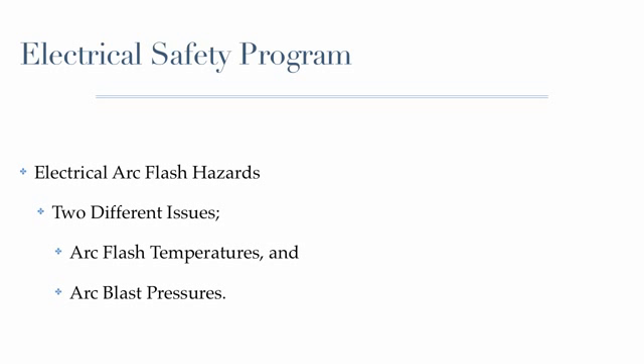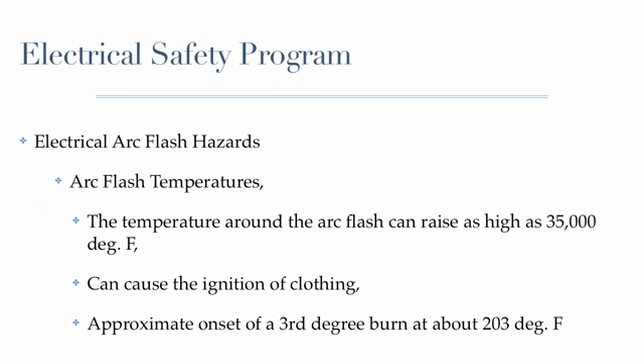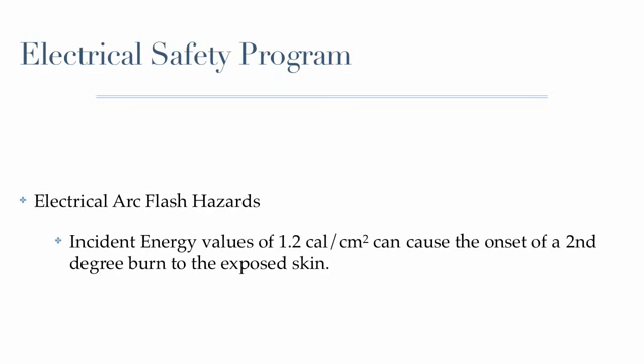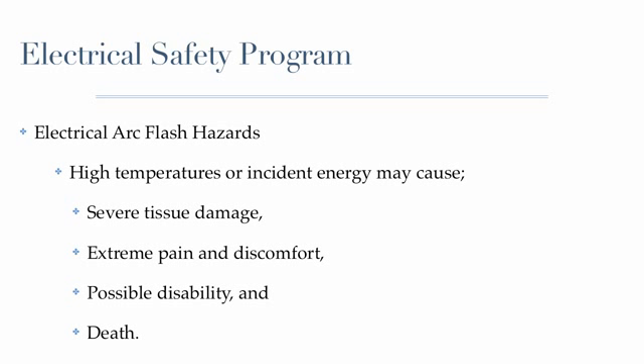There are two different issues we need to look at when we talk about arc flash hazards: arc flash temperatures and arc blast pressures. The temperatures surrounding an arc flash can rise as high as 35,000 degrees Fahrenheit. This can cause your clothing to ignite, and at approximately 203 degrees Fahrenheit can create the onset of a third-degree burn. Incident energy values as low as 1.2 calories per centimeter squared can cause the onset of a second-degree burn to the exposed skin. High temperatures or incident energy may cause severe tissue damage, extreme pain and discomfort, possible disability, and maybe even death.